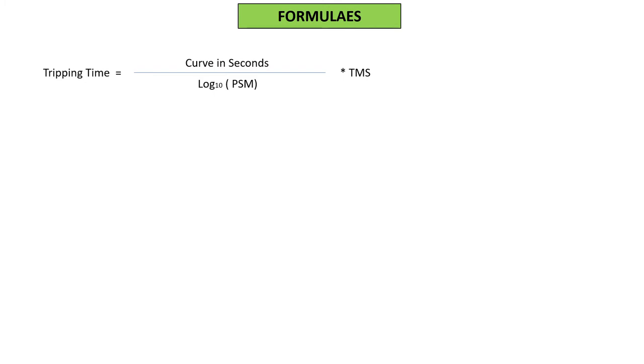Then comes plug setting multiplier (PSM). To calculate this, we need fault current divided by relay pickup value. I am expecting that you know fault current. If you don't know, please mention in the comment box and I will share it separately, otherwise this video will become too lengthy.